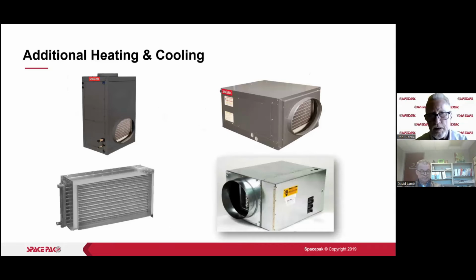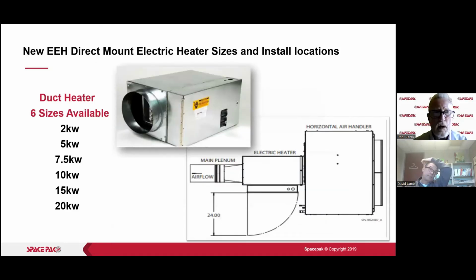Additional heating and cooling. All right, so we've got hydronic coils as shown to the bottom left there. We also have electric heat packages as well. All right. This is the new EEH. It's a direct mount electric heater. It mounts directly up to the air handler. It's available in a wider range than we had before of kW sizes.